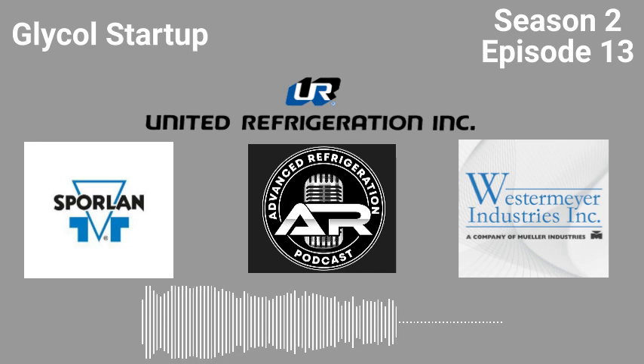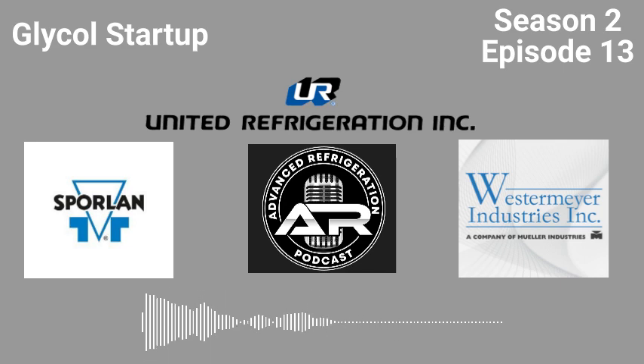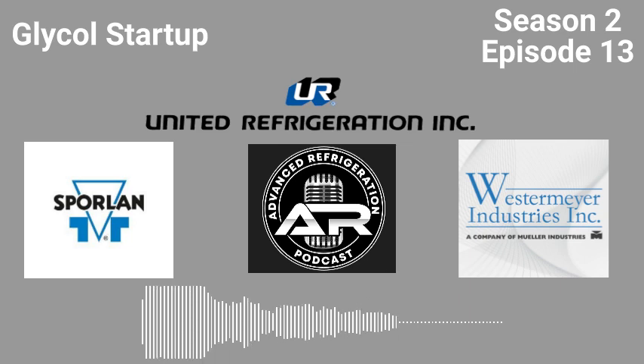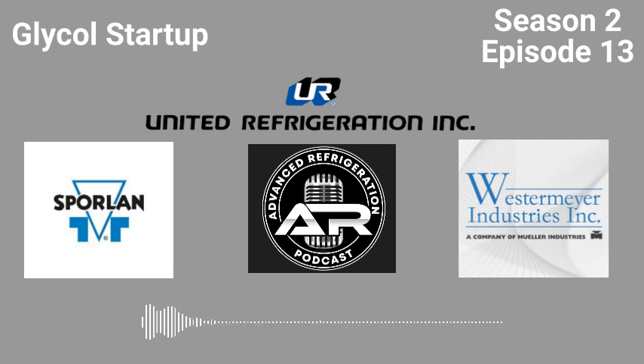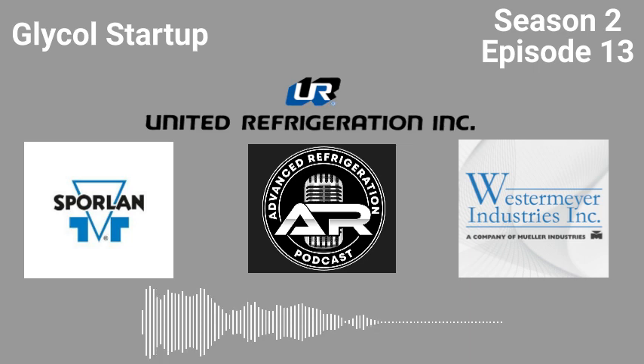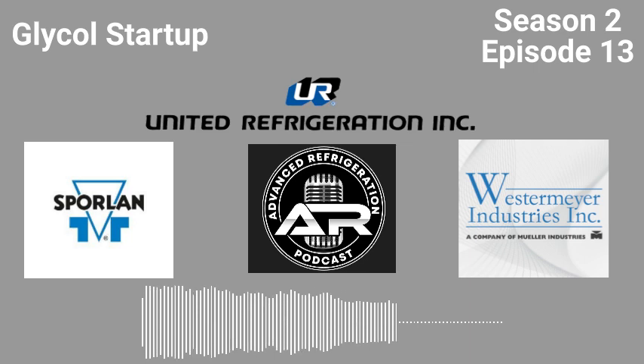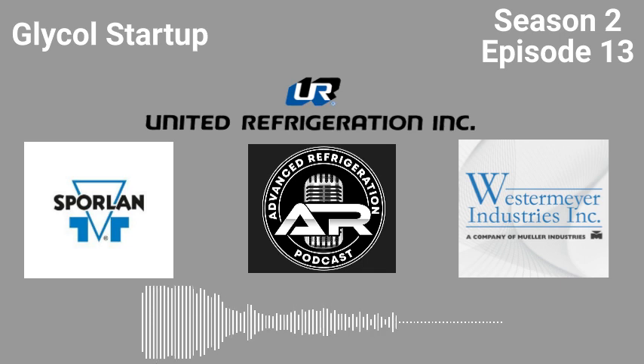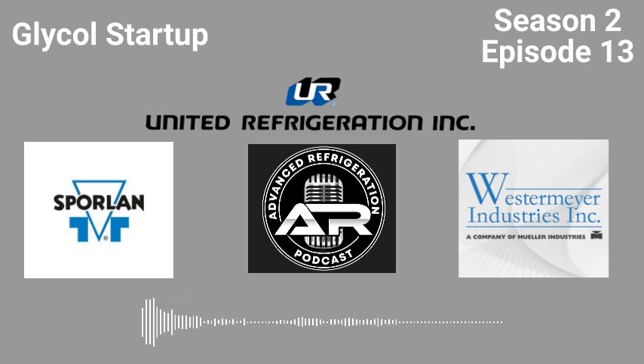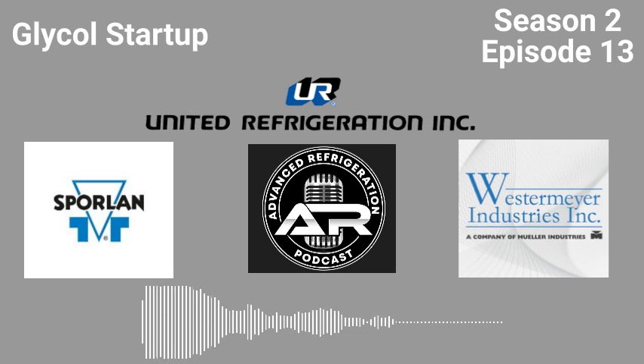I got an idea. Take one of those stores, put a pump out on it, and see if it ever goes bad. Yeah, I don't know. I've never seen the Hill Phoenix one crack. Zero Zone, did you figure it out yet? Let us know. But that's one thing to be aware of if you're doing these glycol startups and you have odd pump pressures and stuff like that, because you could have a warm fluid heat exchanger tank rupture, a chiller leaking.